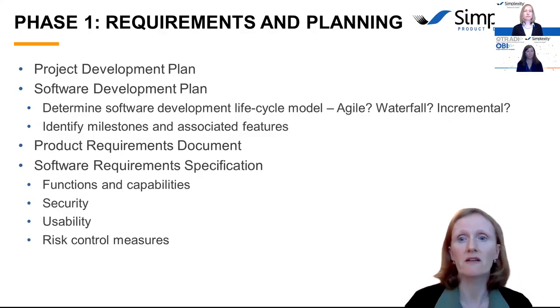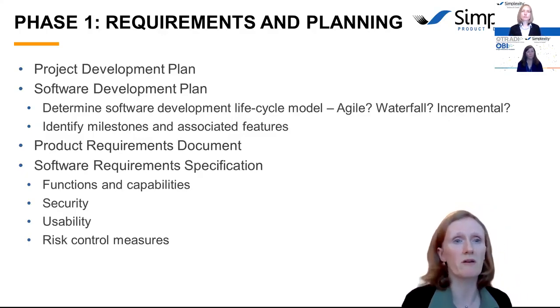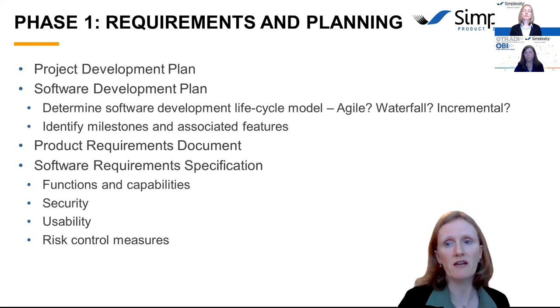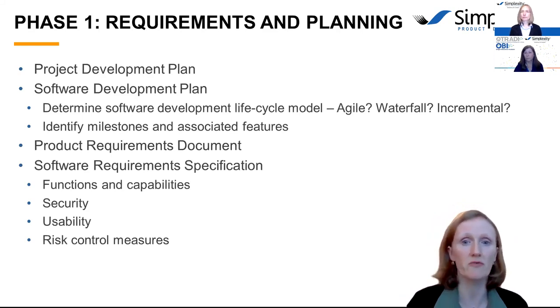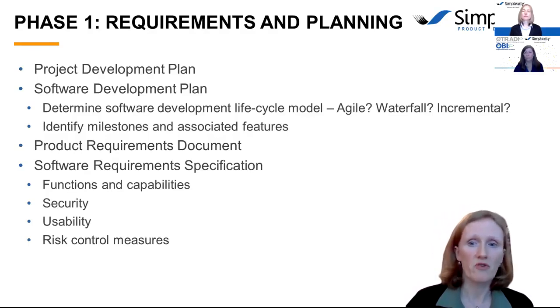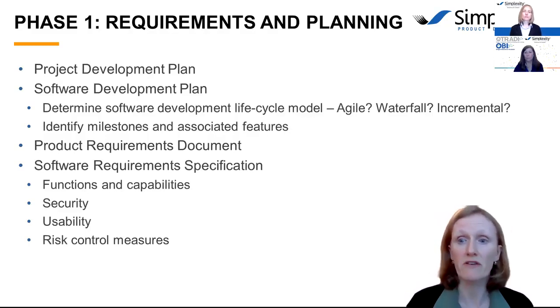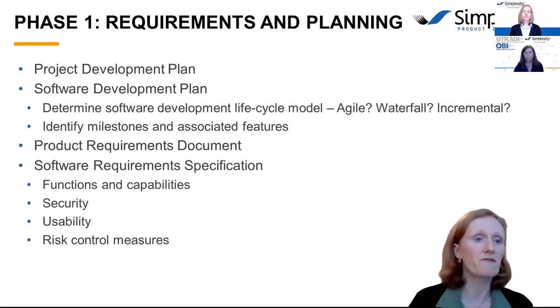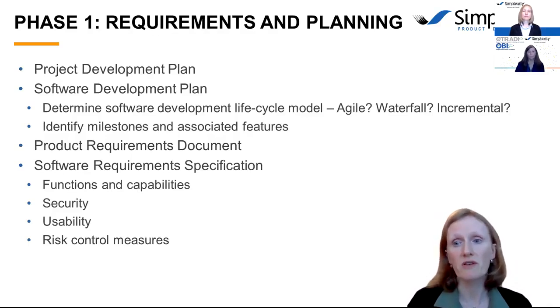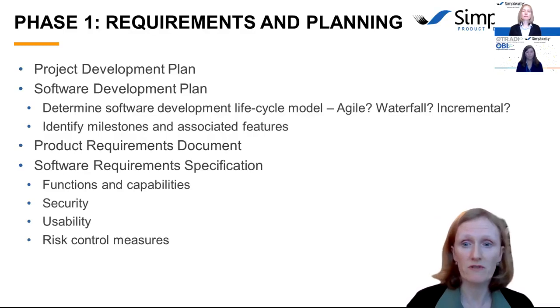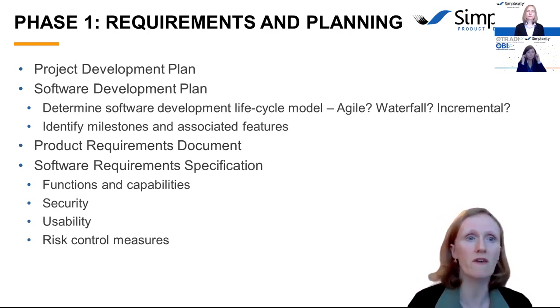The product requirements document takes the high-level user requirements, which maybe came from the marketing department, or in the case of consulting, they came from the client. So you take those user requirements and turn them into specific technical requirements that the engineering team can use to design the product. And the software requirements specification derives from that higher-level product requirements and specifies the functions and capabilities of the software, also requirements related to security, usability, and also importantly, risk control measures. All of these requirements and specifications should be written so that they are testable, unique, and that they cover only one thing per requirement.